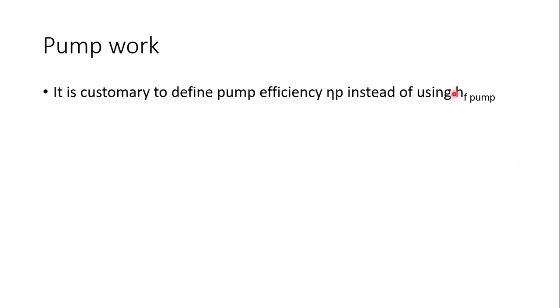So for pumps, we use the efficiency of the pump instead of using the frictional effect in the pump. And we know that the expression for efficiency is the useful amount of energy over the total amount of energy. The useful energy is the total energy minus what was lost because of the friction effect. Just as we said, I can input 100 joules, but because of fluid and mechanical friction, I might get just 94 joules coming out. So I take the total amount of energy minus what was lost or what went to waste. That becomes the amount that I actually used divided by the total amount I put in initially. That will give me the efficiency of the pump.